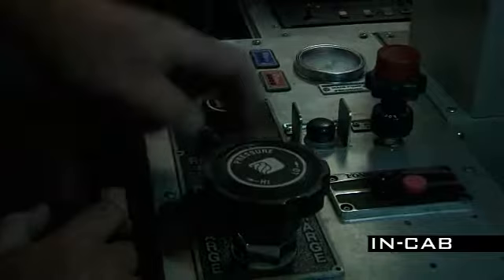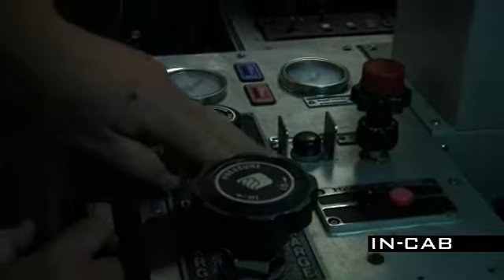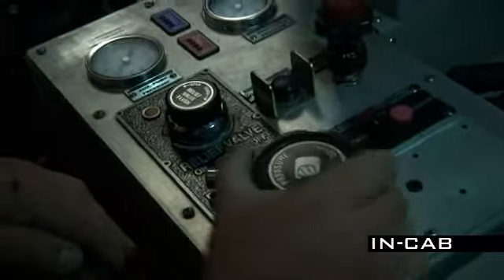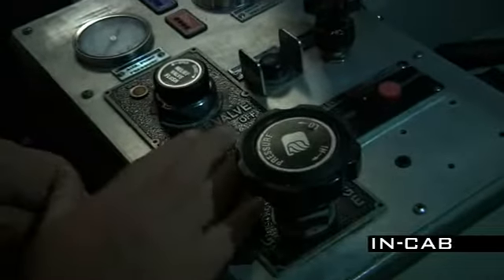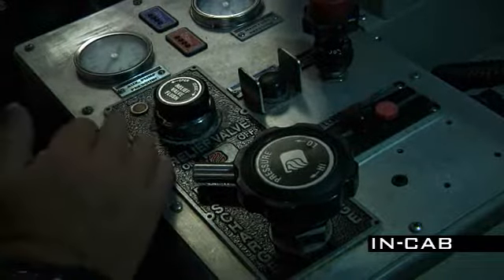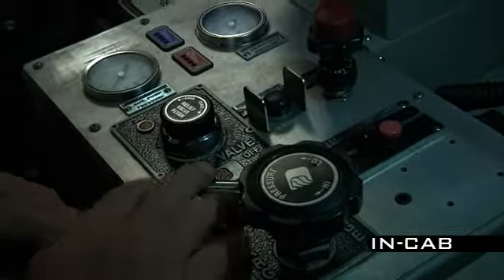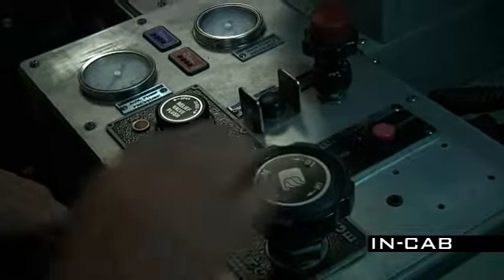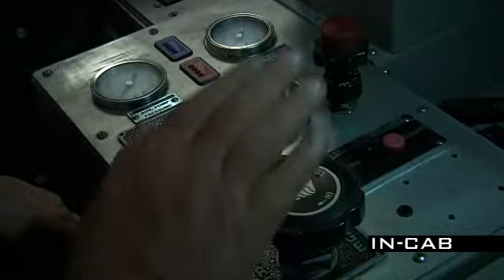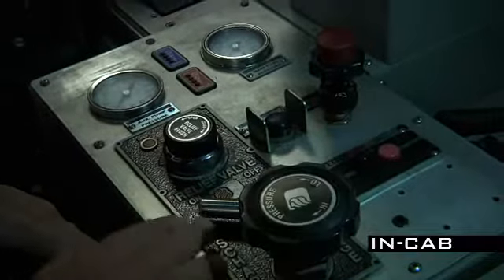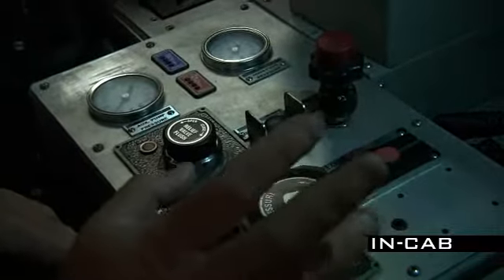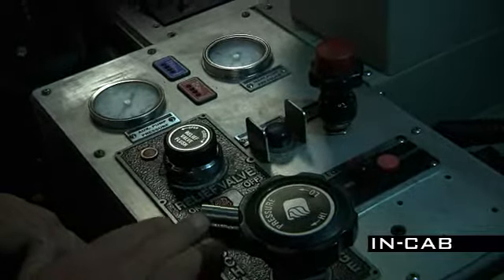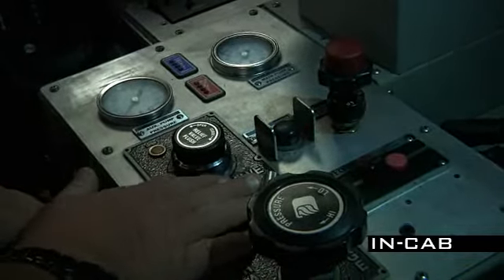We've had some issues in the past with folks accidentally bumping this Darley discharge relief valve and turning it on with it set at an extremely low pressure. If this is on and your parking brake is set, your PTO is engaged, and it's set very, very low, you may not generate pressure from the main pump. So if you are in a scenario where you're not generating pressure in the main pump, you've checked all your checks out on the pump panel, come inside here and ensure that this relief valve is turned off, okay?